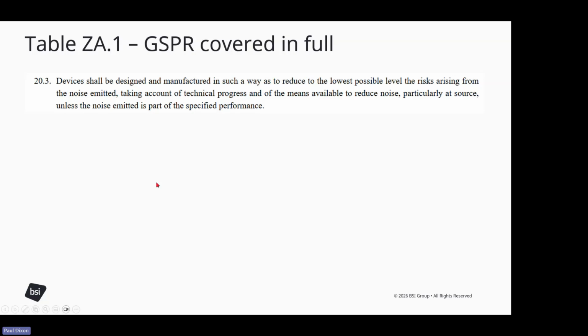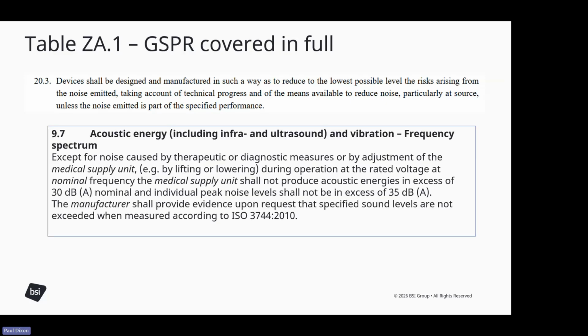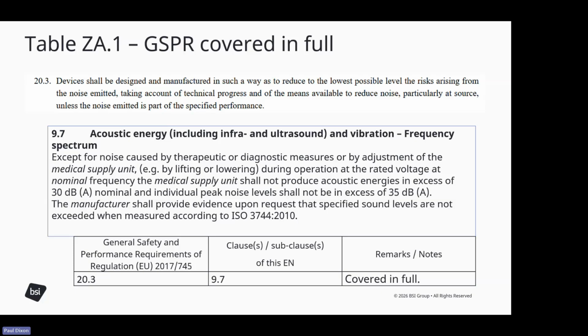So an example, GSPR 20.3: devices should be designed and manufactured in such a way as to reduce to the lowest possible level the risks arising from noise emitted. I'm going to provide you an example from, I think, ISO 11197 medical supply systems. Clause 9.7 of that standard says, except for noise caused by therapeutic or diagnostic measures by adjustment of the supply unit during operation, the medical supply unit shall not produce acoustic energy in excess of, and it provides values. And the manufacturer provides evidence upon request that specified sound levels are not exceeded. So you have a technical solution. You've got defined levels that address the GSPR for noise emission, and we can list that in our Annex Z.